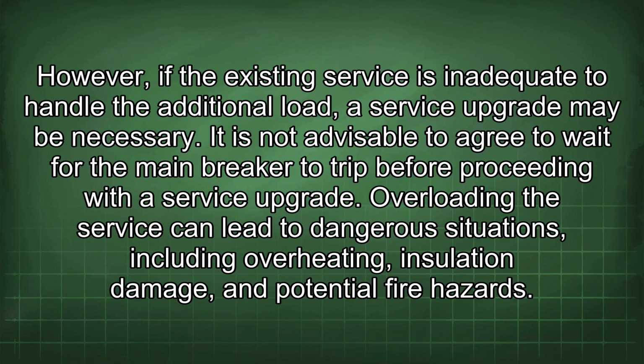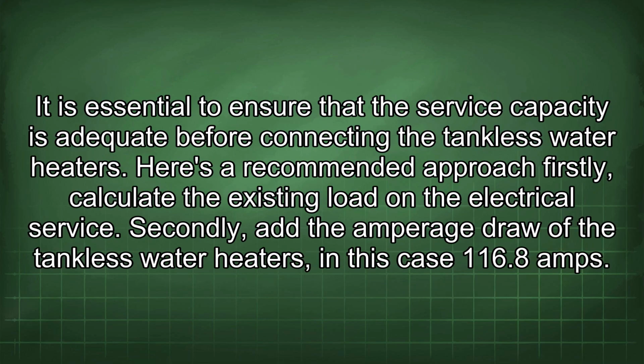It is not advisable to agree to wait for the main breaker to trip before proceeding with a service upgrade. Overloading the service can lead to dangerous situations, including overheating, insulation damage, and potential fire hazards. It is essential to ensure that the service capacity is adequate before connecting the tankless water heaters.